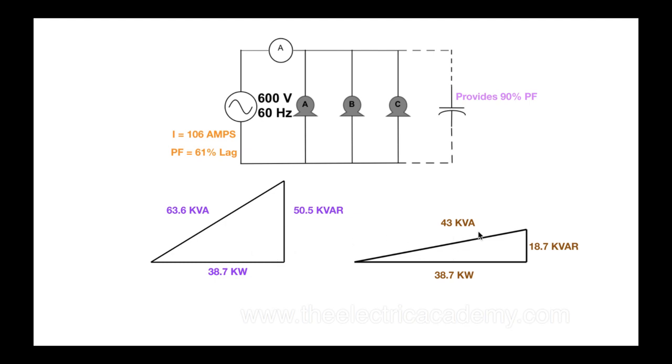Now, if we put that proper size capacitor in here, which I will talk about in a second, then this triangle that we want becomes the triangle that we have. All right, this is the one we had. This is what we want. We put the new capacitor in, and this now becomes the power factor that we have, the triangle that we have. So my amps over here, this 106 amps, those are going to change, and we know that that power factor definitely changes. So let's take a look at that.